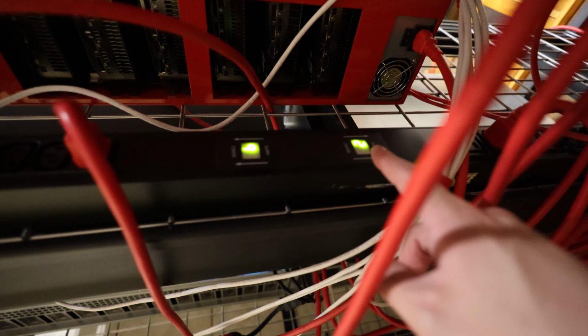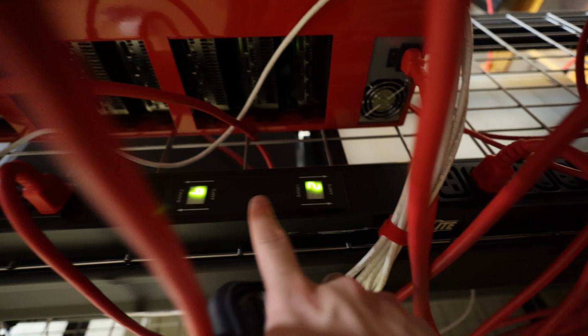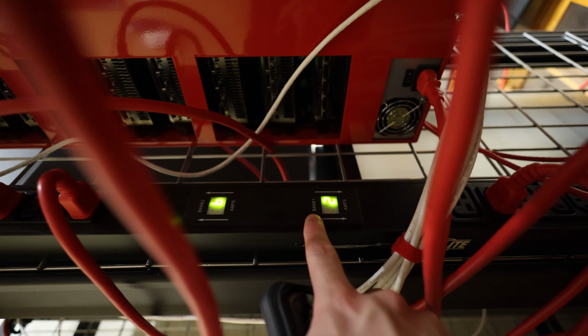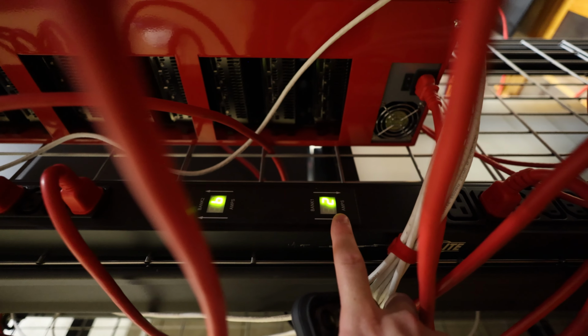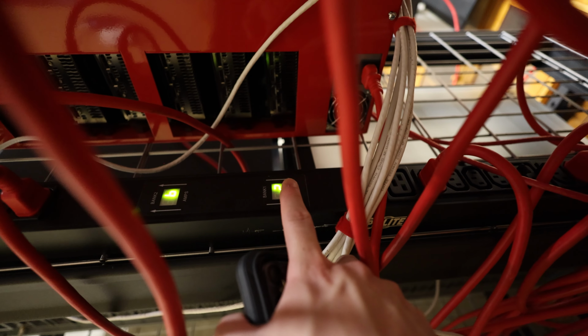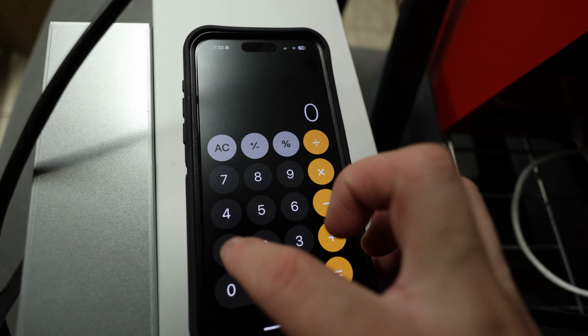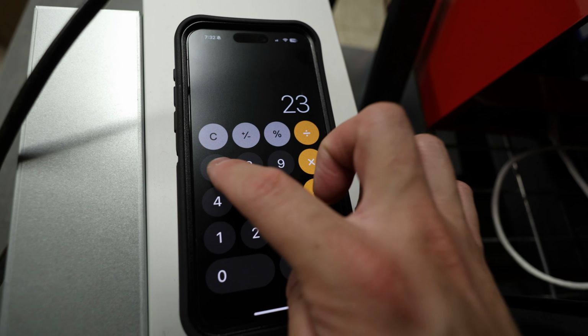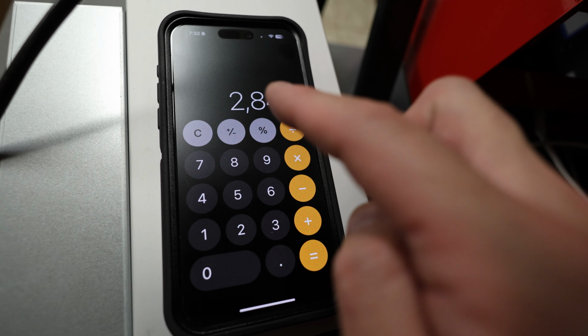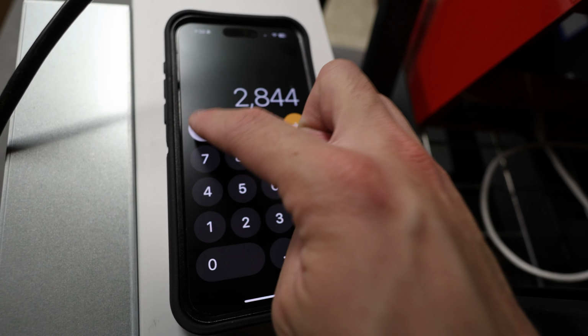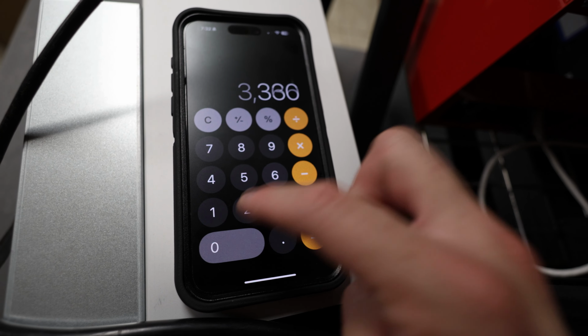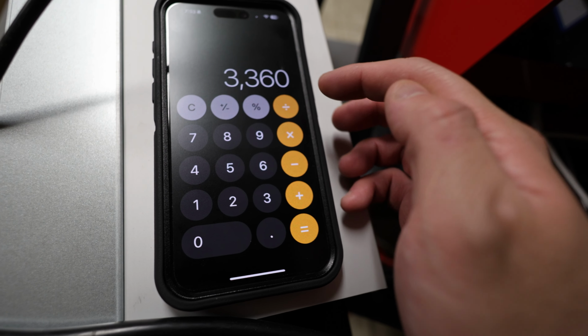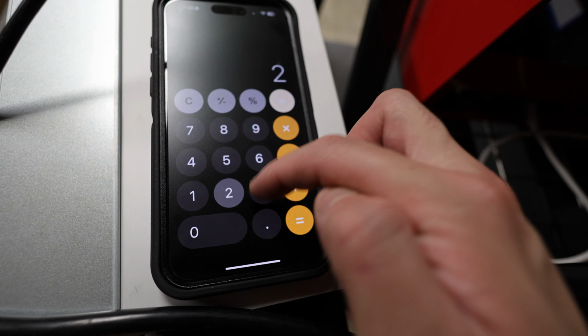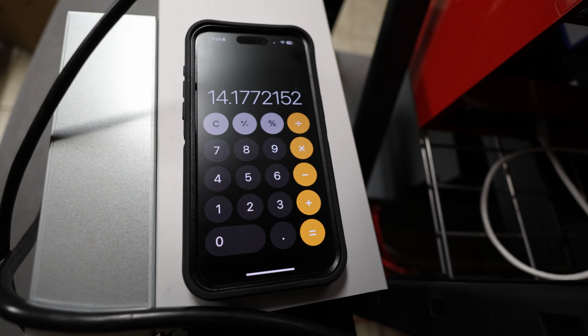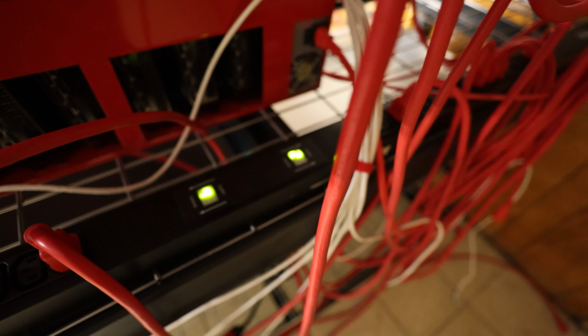This might be tricky. If it's 3,300 watts, let's do the math. This PDU has 2 15 amp banks, but realistically I can use the 80% rule, so 12 amps on each bank. If I use 12 amps on this one, what's 12 times 237 volts? That gives me 2,844 watts. If that Bitmain is advertised at 3,360, it's probably like 3,500 watts or more depending on environment. Divided by 237, that gives me 14 amps. You know what, I'm okay to run 14 amps on this. It should be fine.